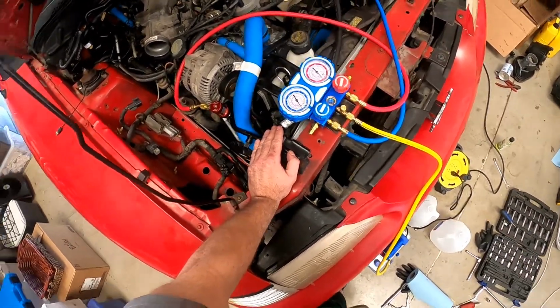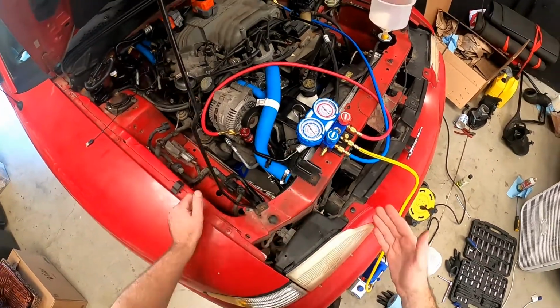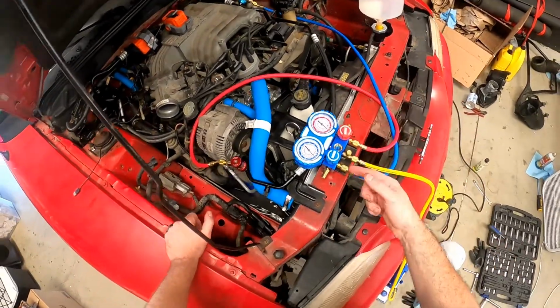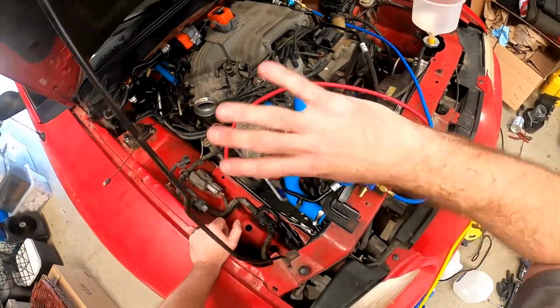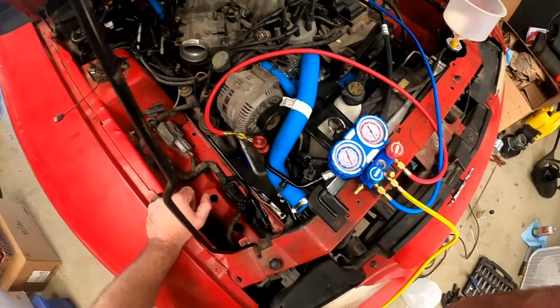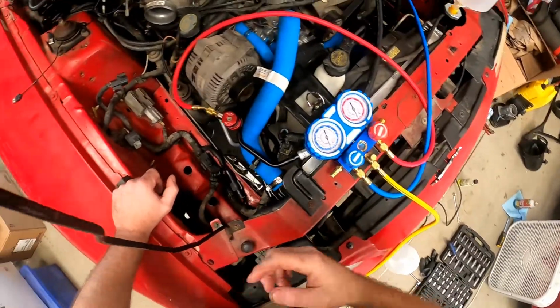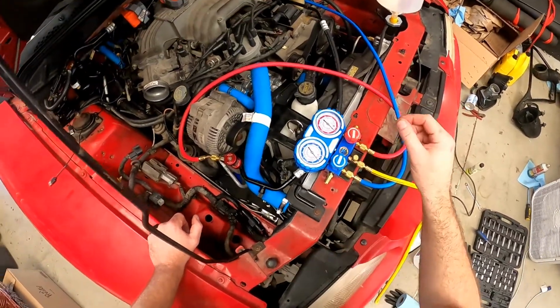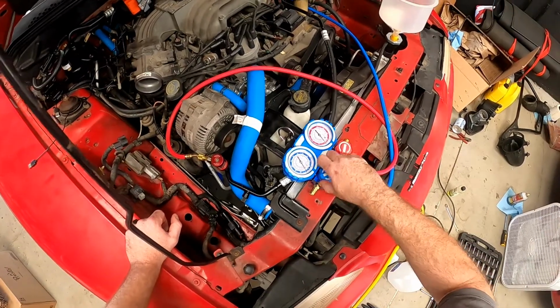What you'll do is vacuum the system out for 15 minutes to make sure it holds negative pressure, to confirm you installed all the fittings correctly. Praying to God that I did, because it's a pain if you have to troubleshoot it. At this point, I'm going to open everything up and vacuum it out.